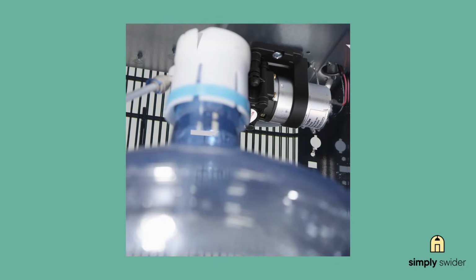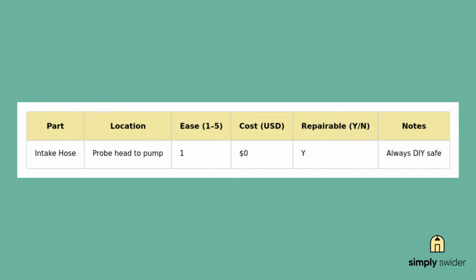Here's the fix. First, firmly push that hose into both the probe head and pump connection until you hear a click. Next, prime the system by holding down each water button for 2-3 minutes. Yes, that long to completely purge the air. You'll hear the pump working hard, and that's exactly what we want. Don't worry about the pump running. That's normal. This one's always a DIY fix, costs you nothing, and honestly saves you from feeling pretty silly when a repair guy charges you $100 to push a hose back in.